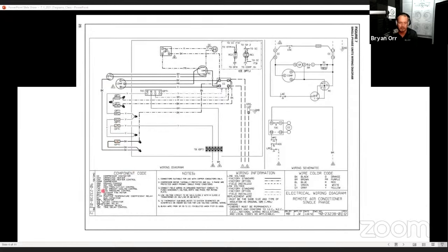A lot of this stuff is really logical. All right, let's take a look at a contact. Contacts are easy. They just look like this. The difference between a contact and a switch, and again, this isn't necessarily universal, but generally speaking, a contact is usually activated in a relay, contactor, or starter by an electromagnetic coil, meaning it's activated by another sort of pilot duty coil. As we know, on a contactor we've got that electromagnetic coil on the bottom. This is an air conditioner, so that's a 24-volt coil, residential single-phase air conditioner. When that 24-volt coil is energized, the circuit is made on the Y circuit, goes back to common on the other side, then it's going to close this switch.